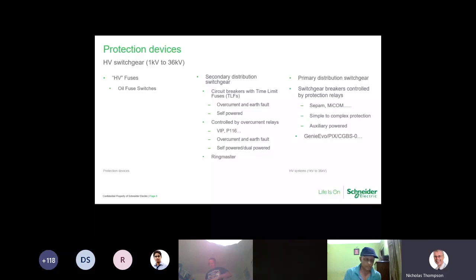So if we start to look at secondary distribution switchgear, this is the likes of your classical ring main units or simple switchgear, which is not going to have great requirements on protection or control. So the protection requirements within those types of equipment are going to be relatively simple. So we've got time limit fuses, or we've got self-powered relays. Sometimes we need an auxiliary powered relay as well, so dual powered. So the primary protection is self-powered from the CTs, and then for other functionality within that relay, it would need an auxiliary power supply.